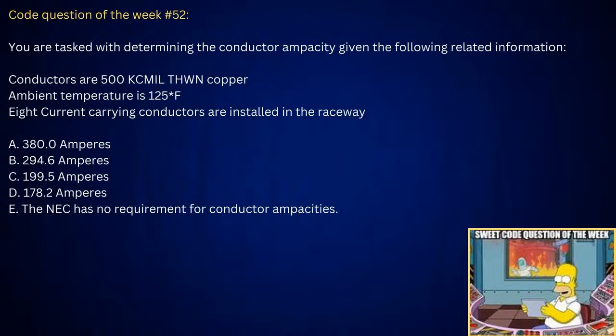Now, the next one is the ambient temperature. So I'm going to look at Table 310.15(B)(1). Come down, I'm going to look at 125 degrees. You're going to be right in the 123 to 131 range. Now, what a lot of people do is come across and use the 76 percent, but this is the 75 degree C column, so I'm going to take that at 67 percent. All right, so I've got that down. Now he's got 8 current-carrying conductors, so I'm going to look at Table 310.15(C)(1). Come down, you'll have 7 to 9 conductors. It's going to tell you to take it at 70 percent. Oh, 70, right. So I'll take 380. Just give me a second to add it up here. Times 67 percent. Times 70 percent. That's going to be 178.2 amps, so your answer is D.